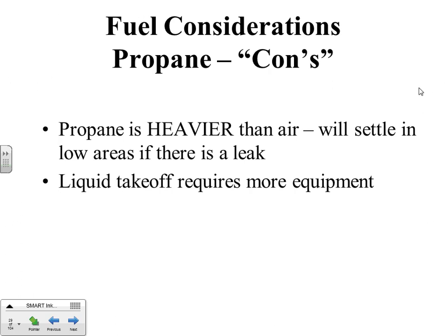On the con side of propane, propane is heavier than air, and it will settle in low areas if there's a leak. When I was in Oregon, I did a lot of mountaintop repeater sites, radio repeaters, and a lot of telephone companies have repeaters on the top of the mountains. And there was one installation where they had a propane unit inside the building. And this was back in the days of a lot of relays instead of highly digital. And they had a propane leak. Luckily, this was an unmanned station.